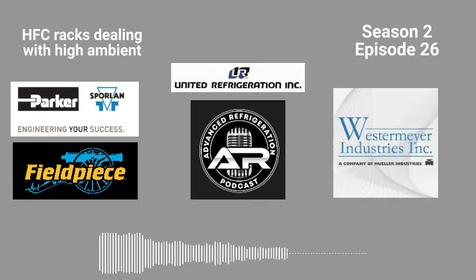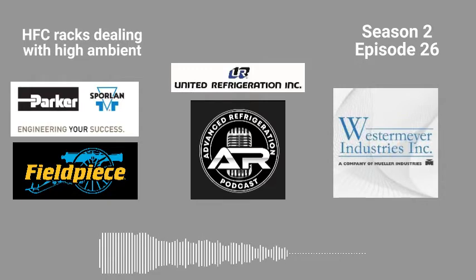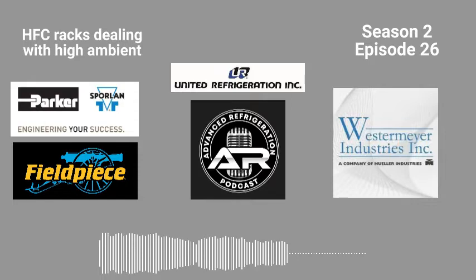Absolutely. With a glided refrigerant, I usually go plus or minus 3 or 4 degrees of the midpoint. Yes, absolutely. I've never done a non-condensables test where it came up either straight liquid or straight vapor. It's always midpoint. You've got to remember some of these refrigerants have huge glides, but 3 or 4 degrees from midpoint. Now, what you want to do, go ahead, Brett. Oh, no, you finish that, because I just want to make sure that I hit on something that could be causing high discharge pressure. Go ahead, continue.